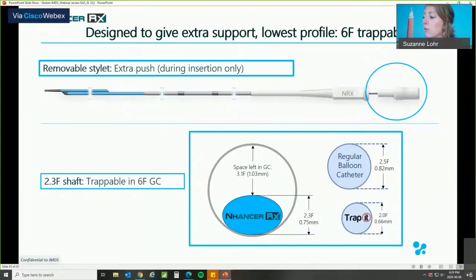Looking at the profile, which has been discussed in this webinar before, the profile of the NHancer RX is 2.3 French only. This makes it trappable in a 6-French guiding catheter because, as you can see, the space left in a guiding catheter is more than 1 millimeter, and a regular balloon catheter is 0.82 millimeter on average. So a regular balloon catheter can always fit next to an NHancer RX in a 6-French guiding catheter. Also, a Trapit can be used, which I will explain in a minute. To summarize very shortly, the NHancer RX dual lumen microcatheter has fully visible exit ports in the distal end, and by the removable stylet, it has a lot of push while keeping the profile low. It is always trappable in a 6-French guiding catheter.